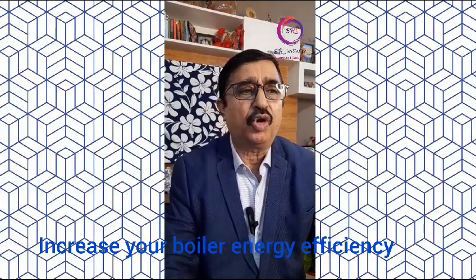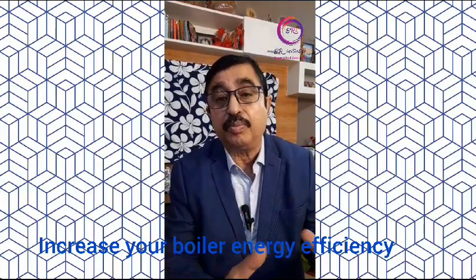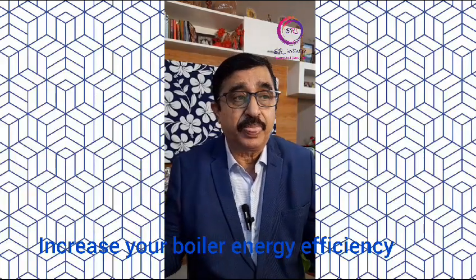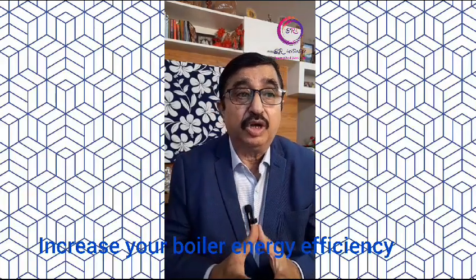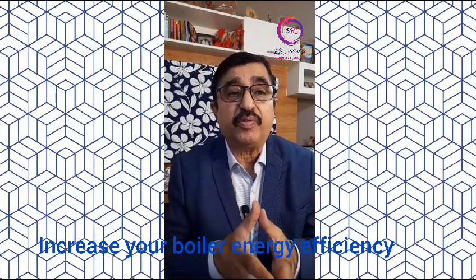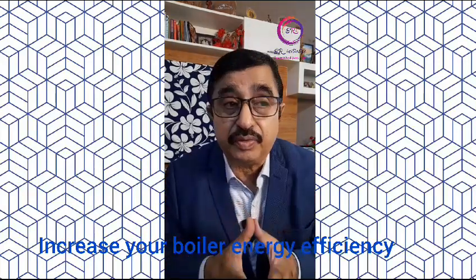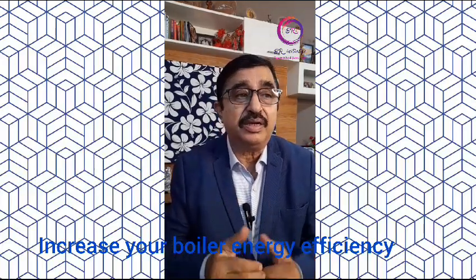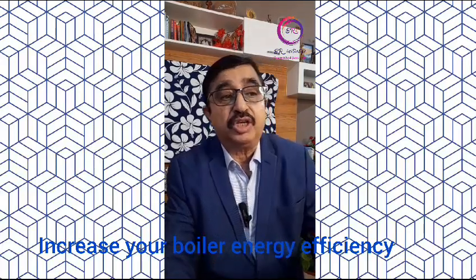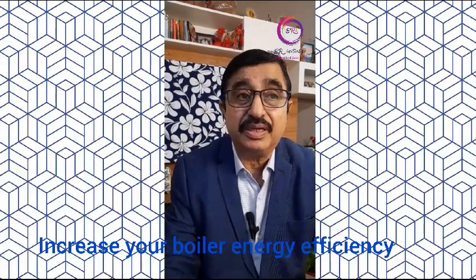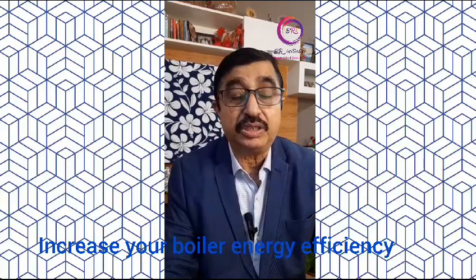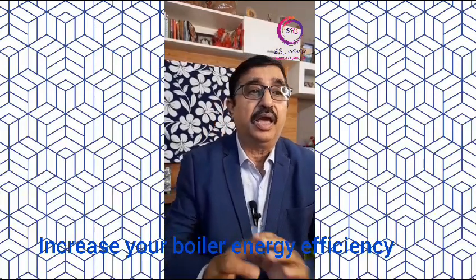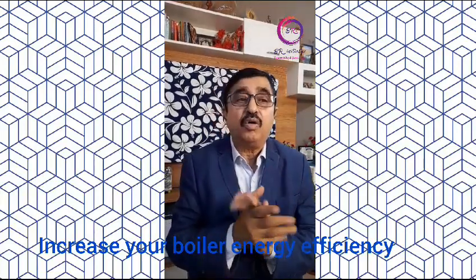In a simple way, following are the losses from the boilers. When you calculate the boiler efficiency by the loss method: the percentage heat loss due to dry flue gas, the percentage heat loss due to evaporation of water vapor formed due to the hydrogen in the fuel, the percentage heat loss due to evaporation of the moisture present in the fuel, H2O, the percentage heat loss due to moisture present in the air, losses due to carbon monoxide, losses due to surface radiation and convection, and other unaccounted losses.